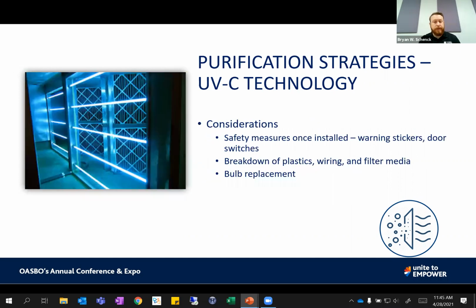Considerations - there are some safety measures that need to be in place if you were to install UVC technology within your mechanical equipment, mostly because this light is harmful to us. We've actually had technicians in the field who didn't know there was UV equipment in there, and they opened the door, and it's really harmful to our sight and eyes for the short term, even if only exposed very quickly. So having switches and stickers that notify people working on that equipment is very important to protect those people. Because it's volatile, it's going to break down plastics and wiring and media in the locations where it is - it's something to think about.